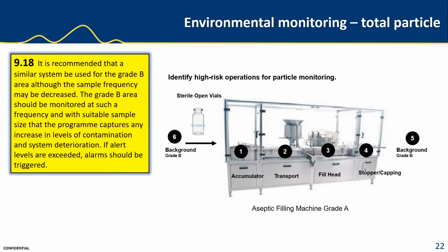And even though the guideline says the sample frequency may be decreased, further down that guideline, it calls for continuous monitoring of grade B, as we'll see, as you need to capture any increase in levels of contamination, and you can only do that by continuously monitoring and trending of the data. So this section, to me, is a little contradictory. However, in practice, the norm in the pharma industry especially is to continuously monitor grade B locations. And here we see locations 6 and 5 being monitored.